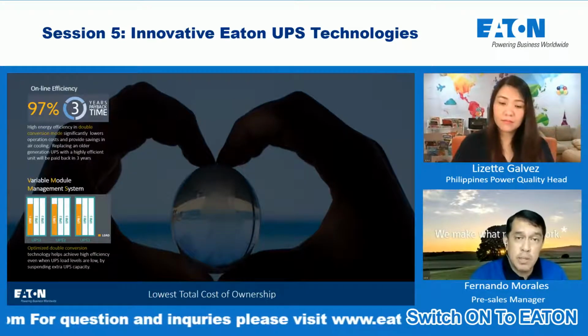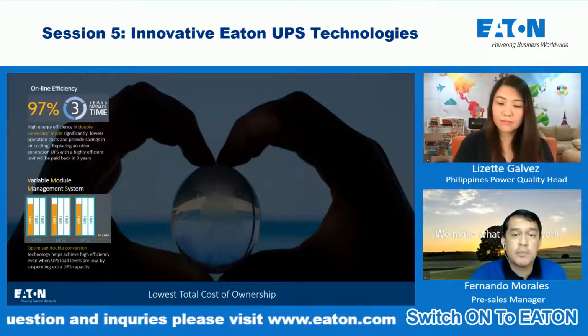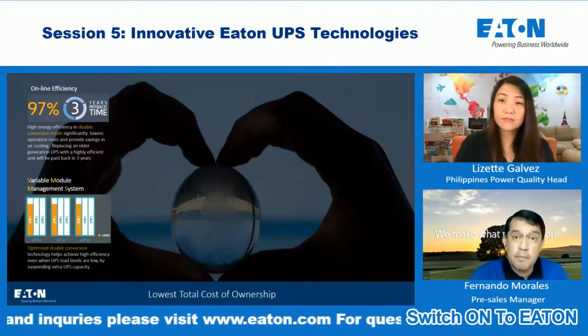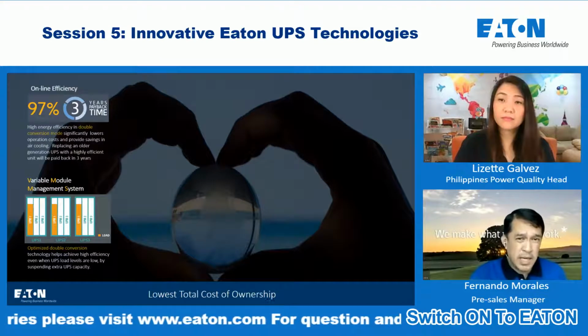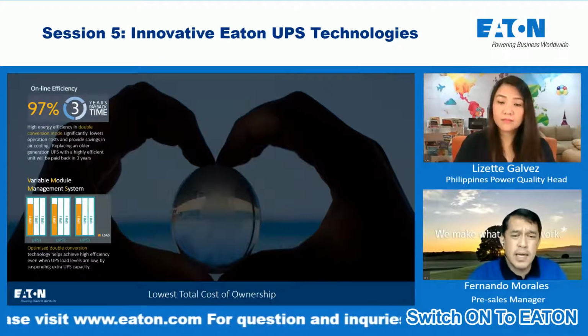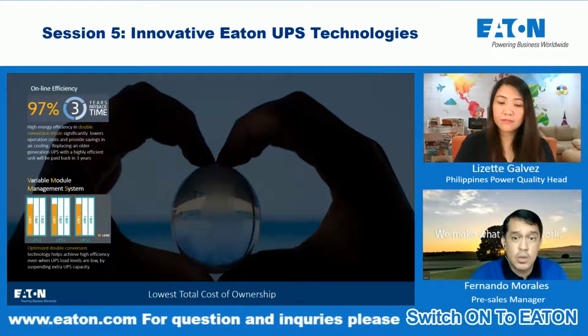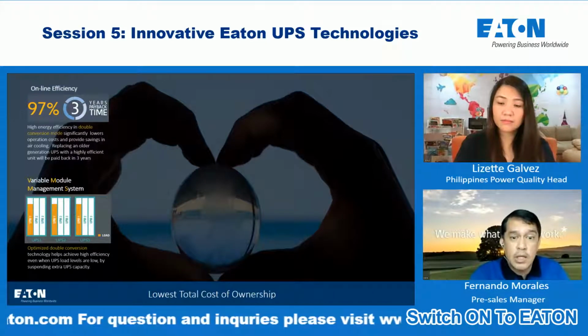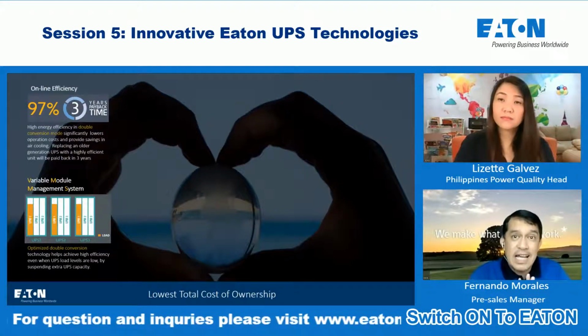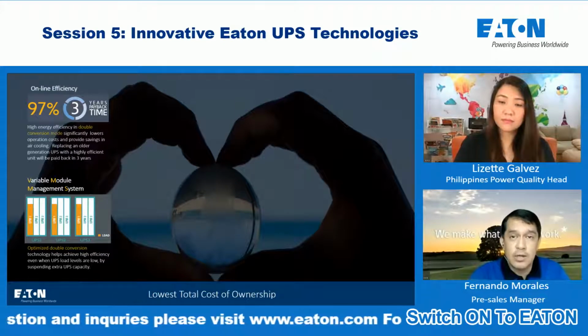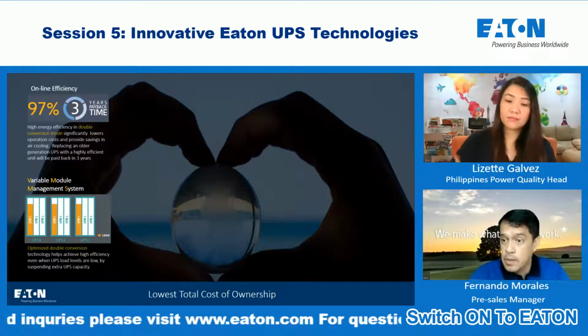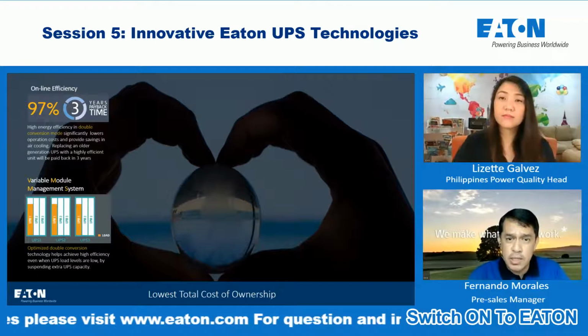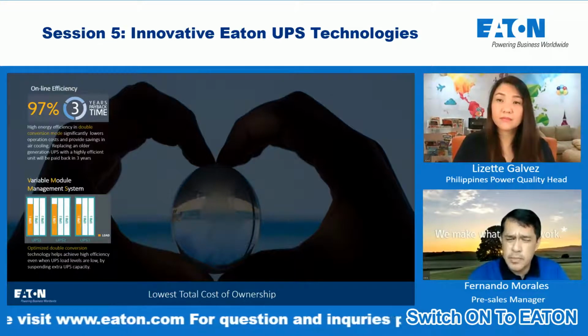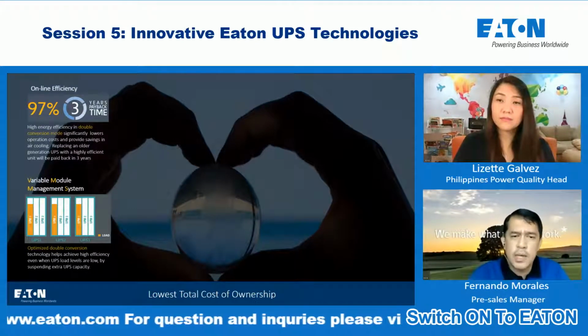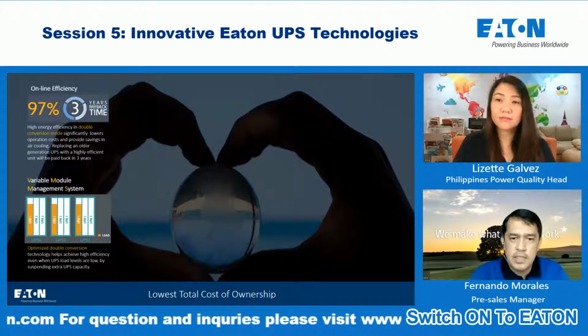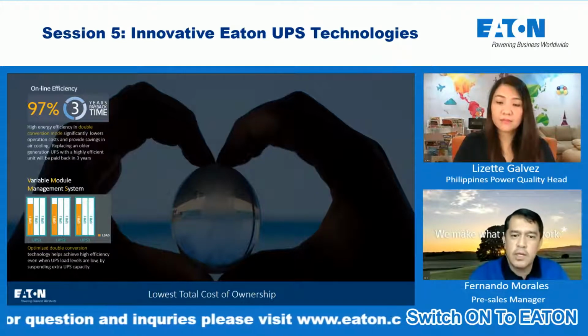VMMS can optimize the load levels of our modules in a single UPS or in parallel UPS systems by suspending extra UPS capacities or modules. The result is an optimal online efficiency at all load levels. That's VMMS, available in our three-phase modular UPS systems only - for monolithic, we don't have this feature.